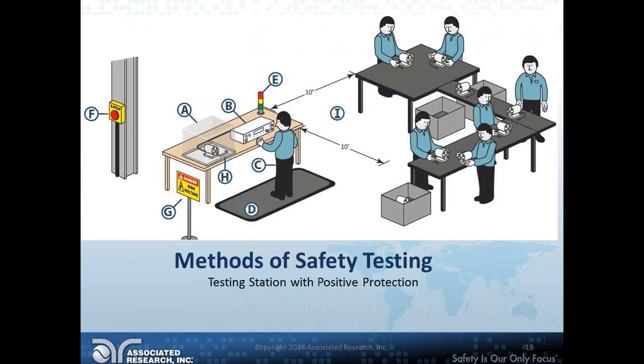You'll notice there that I also have the 10-foot number there, which I'll get to in a second. F is an emergency stop switch for the high pot testing station, so that if something goes wrong, somebody can hit that E-stop and shut down the station. G is a high voltage sign, which I recommend: if you have a high pot testing station with others in the immediate area, get one of these signs.